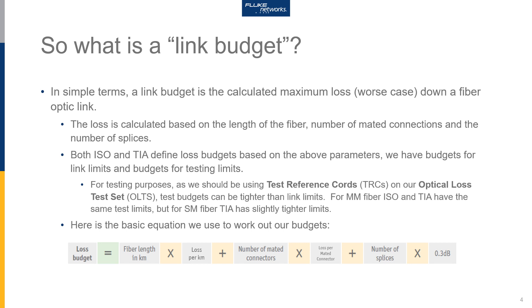When it comes to testing, best practice is to use test reference cords with your optical loss test set, or with your light source power meter combination. Budgets for testing can be tighter than link limits, especially when it comes to multimode fiber. From a standards point of view, both ISO and TIA organizations have the same test limits, but for single-mode fiber the TIA organization has slightly tighter budget limits.